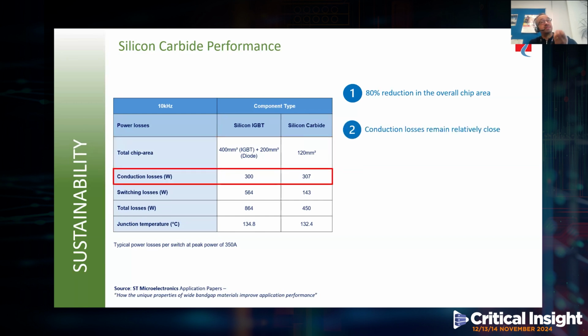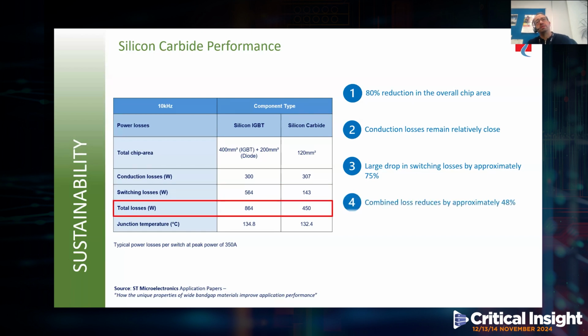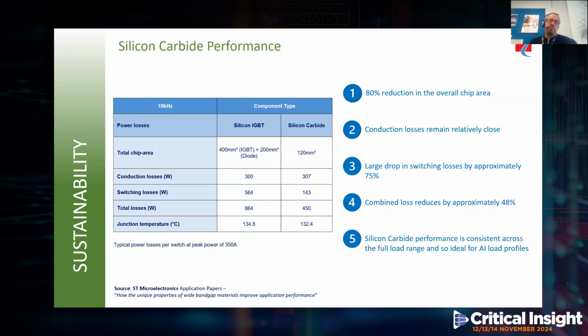The conduction heat losses are very similar. In fact, silicon carbide is slightly higher. Now, the switching losses is where the main gains are achieved, where we see a drop of 75%. And when we add all these figures up, we see an overall and combined reduction in heat loss of about 48%. And finally, one of the main benefits of silicon carbide is that its performance is consistent across the full load range. And so it is ideal for UPS applications and especially beneficial for the up-and-coming AI load profiles, to maintain a very high level of efficiency as the load demand is permanently changing.